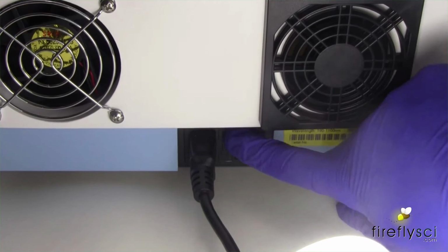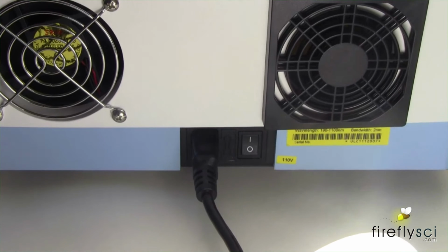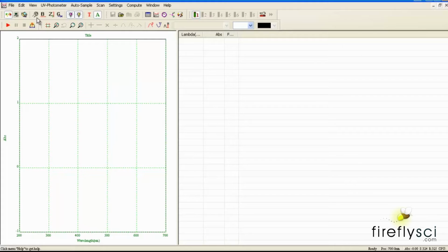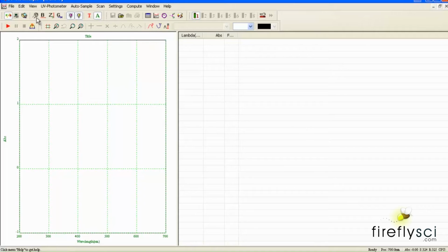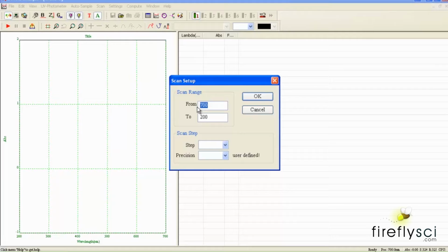Let's go ahead and turn on the spectrophotometer and let it warm up for 45 minutes. I'm going to use the software that came with our spectrophotometer since it's easier to see the peaks. As always, you should check your manual to see the wavelength calibration procedure for your machine. So I set the machine into wavelength scan mode, and I set the scan range from 200 to 700 nanometers.